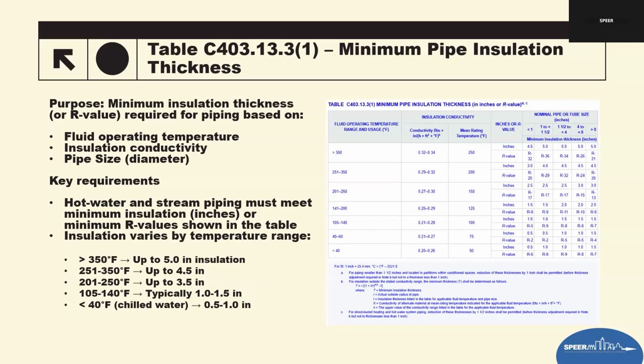So adjustment notes, there are 3 key adjustments here. Small pipes and interior partitions can reduce insulation by 1 inch, but never below 1 inch. If the insulation used has a conductivity outside the range, the code provides a formula to calculate the equivalent thickness. Direct buried systems may reduce insulation by 1.5 inches, but again, no pipe may have less than 1 inch of insulation total. These adjustments allow for flexibility while maintaining minimum performance.